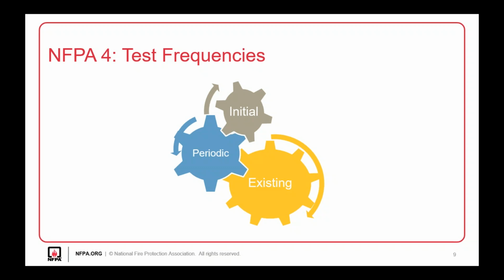The last thing on testing frequencies: NFPA 4 has a provision stating that if your jurisdiction adopts NFPA 4, within 5 years of adoption a test plan is required to be developed. I want to be clear that the test plan has to be developed within 5 years—that doesn't mean the test itself needs to be conducted within 5 years. The plan can specify a frequency or interval that makes sense for your building, determined by the integrated testing agent, the owner, and the authority having jurisdiction. So if your jurisdiction adopts this in 2020, you have until 2025 to develop a test plan, and within that plan you could specify testing every 10 years, for example. It just needs to be developed within 5 years of adoption.